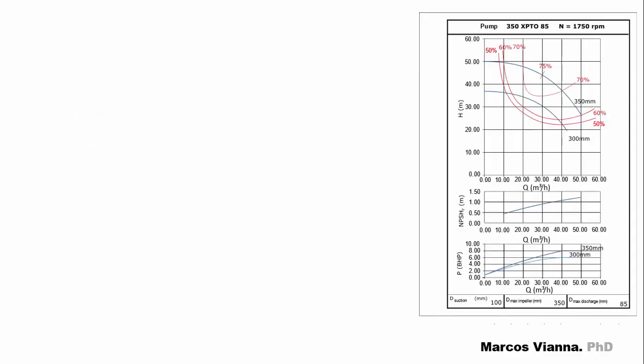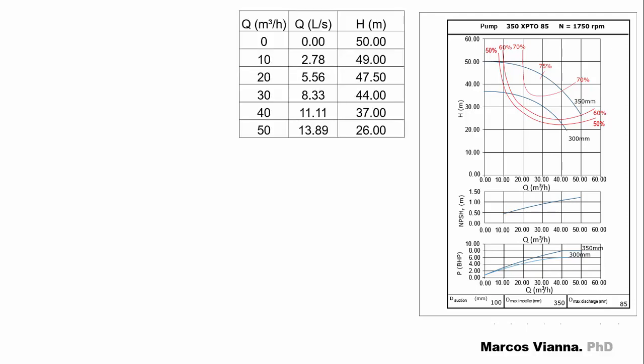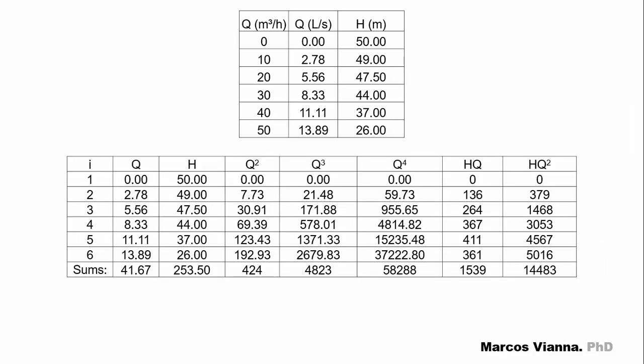Okay, now we're able to fit a second degree polynomial function to the pump curve corresponding to the 350 millimeters impeller diameter. Here are some Q and H values extracted from the pump chart, and we put them in this table. The Q values are in liters per second. We also calculate the values of the other columns. It's easy to do it in a spreadsheet software, such as Microsoft Excel.